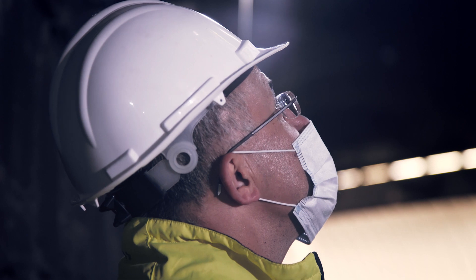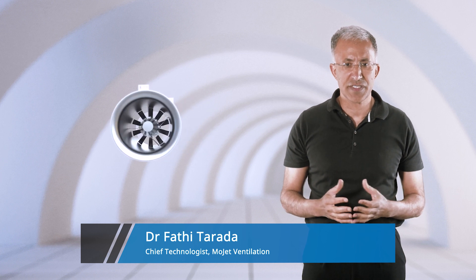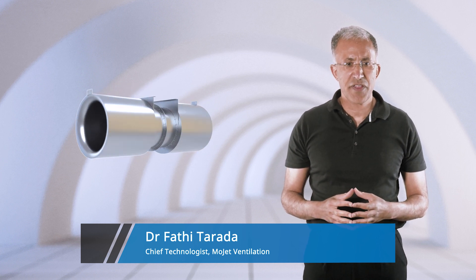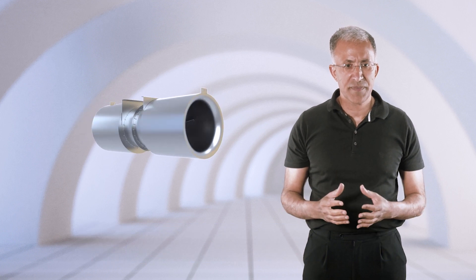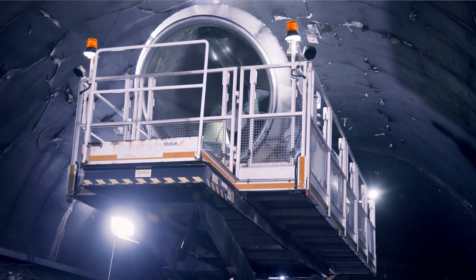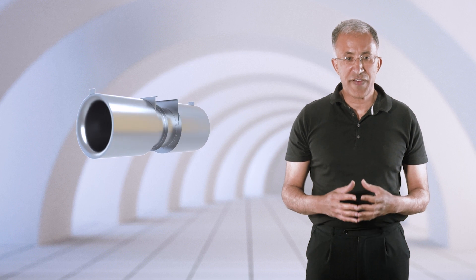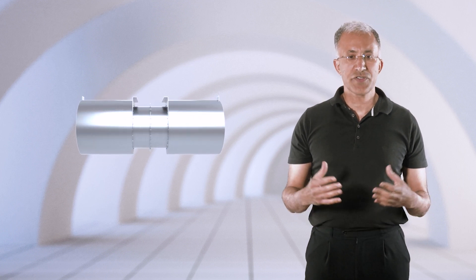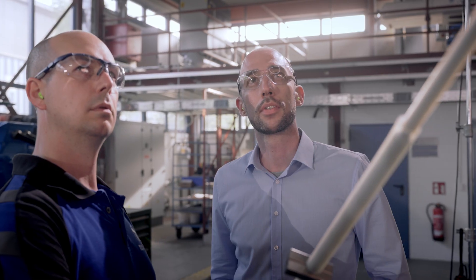As a designer of tunnel ventilation systems, I was frustrated by the fact that jet fans are inherently inefficient, typically losing between 30 to 50% of their thrust through friction between the jet and neighbouring tunnel surfaces. What we needed was a compact solution to deflect the jet without reducing the bench thrust or increasing the power consumption or noise.